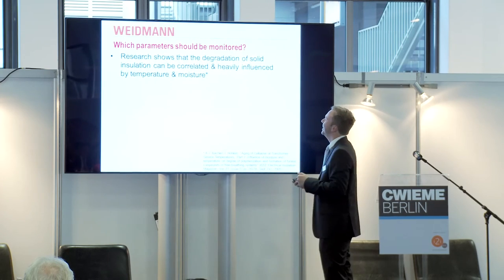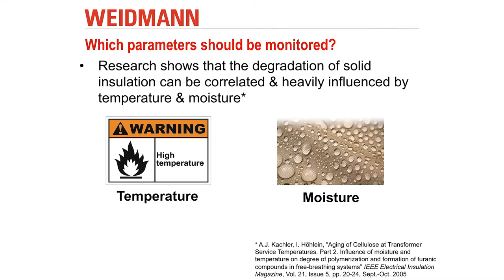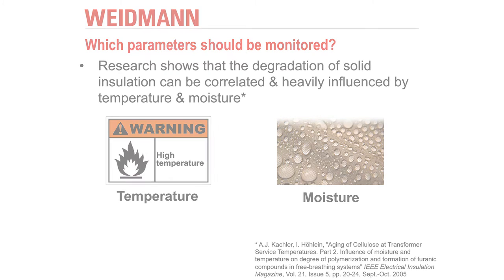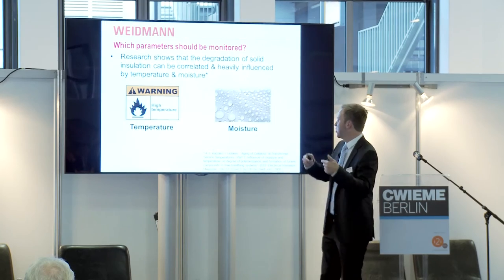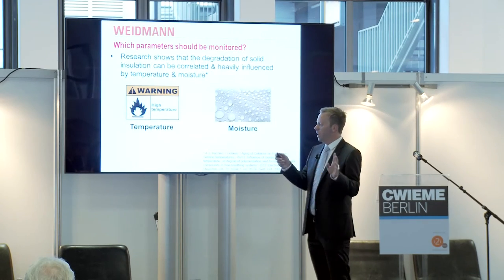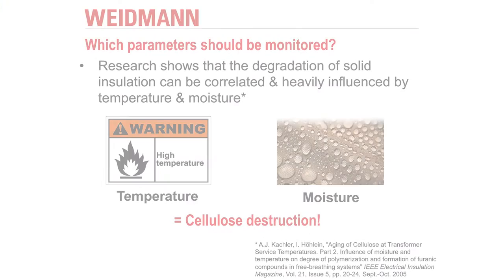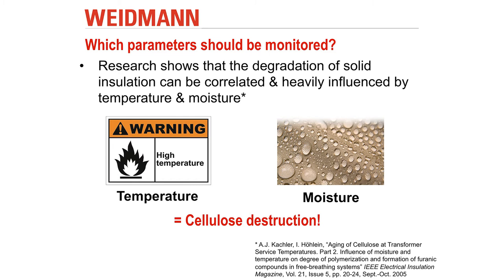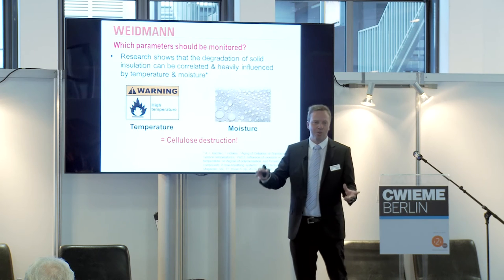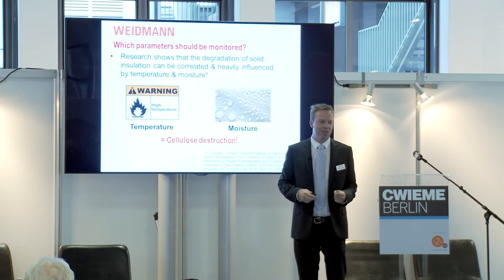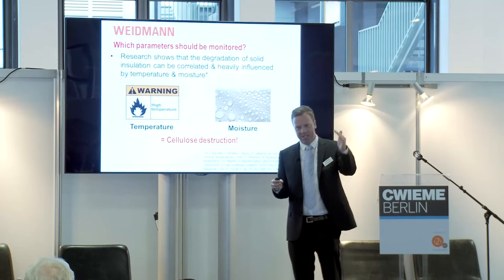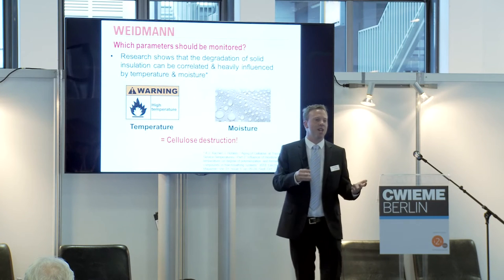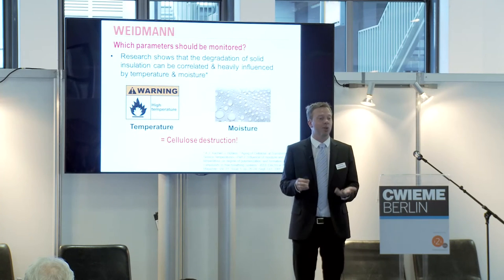That's fine, so we have temperature and moisture. What does temperature and moisture within a transformer mean? Well, now we're going to get some Hollywood dramatic cellulose destruction. Temperature and moisture in the transformer create destruction of cellulose, which ultimately reduces the DP value, meaning the transformer is aging and will eventually fail.